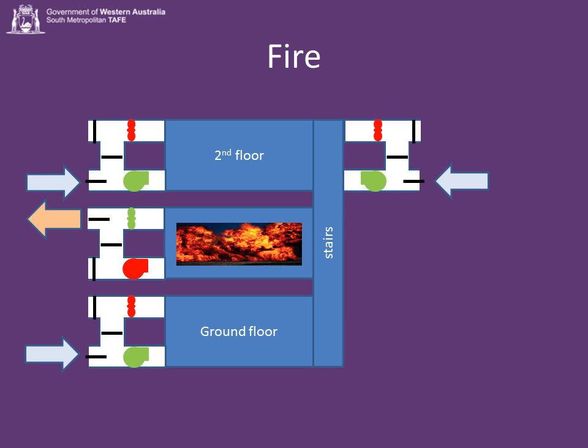We also pressurize the stairs so that no smoke gets into the stairwells and the emergency exits. When we're doing this pressurization, we have to be extremely careful that we don't over-pressurize areas, because if you over-pressurize something, you can't open the door. So we have to make sure that we test the doors so that they will open. There's specific scales and ways of testing this. I would recommend you go to your local building codes to find out what pressures you need to be able to open the doors. And with sandwich pressurization, everybody not in the area where the fire immediately is will be getting fresh air and no smoke. And hopefully they'll get out.